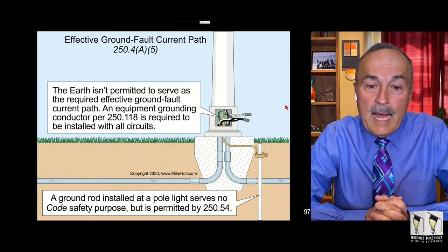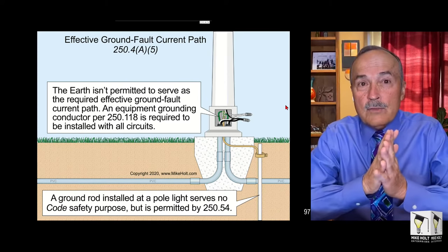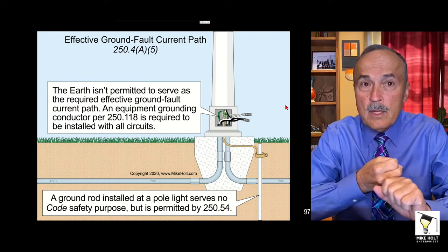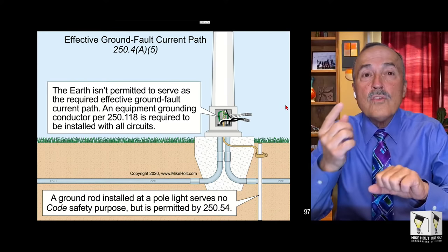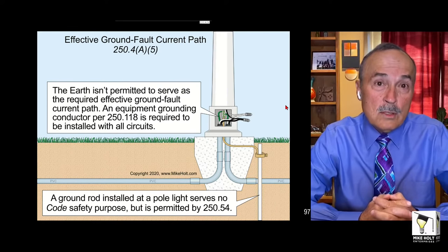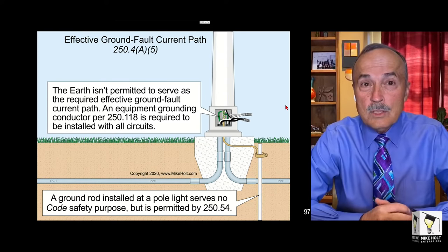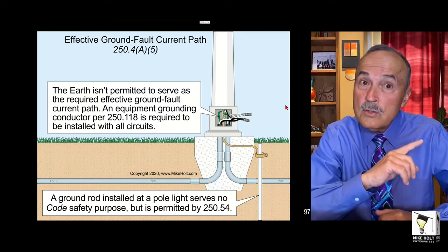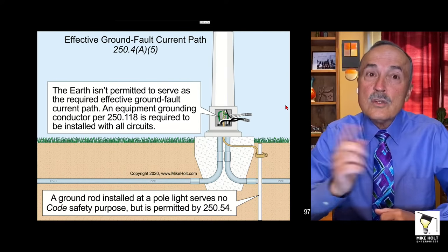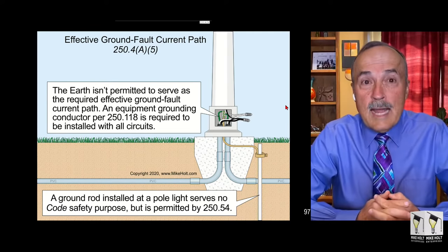Effective Ground Fault Current Path - that's a term defined in Article 100 as well. The effective ground fault current path is an intentional path created to provide a low impedance path from the point of a ground fault back to the source. It's for the purpose of clearing a fault. When you have a ground fault, that fault current is returning to the power supply - the transformer, either utility transformer or a secondary transformer. If you have a low impedance path from the point of the ground fault to the source...